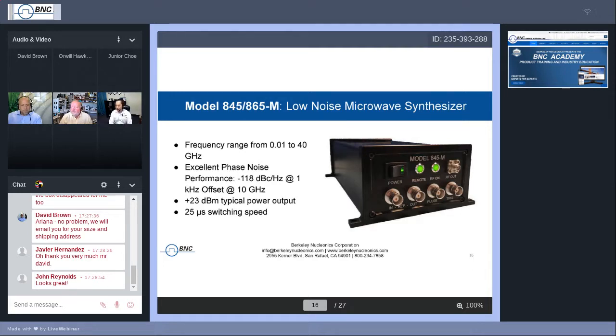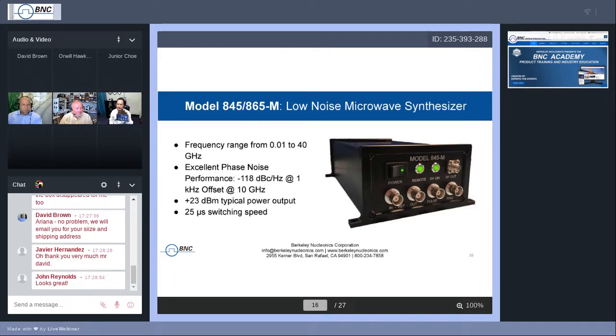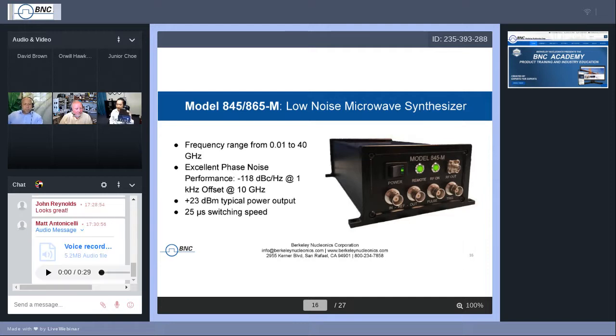I must mention our low noise microwave synthesizer. This is PC control only, much smaller than the bench top. It's easily integratable into any system or can be used as your LO — an excellent phase noise CW source for many different types of applications. The specs and phase noise are all there: 40 GHz, and even the power is quite good — plus 23 dBm across the frequency range — with very fast switching speeds again.